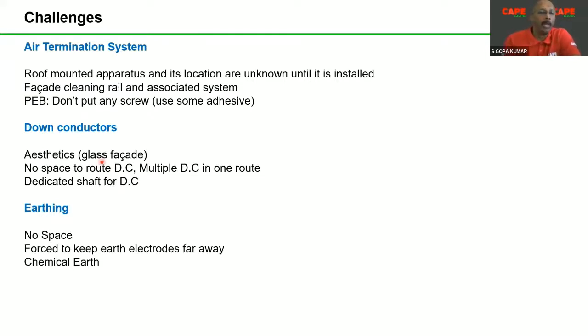You route all the down conductor through one side of the building. So all the three sides are glass. You cannot touch that particular part. Your whole lightning protection down conductor has to be routed through one side. Practically, this is a violation of the standard. Your lightning protection system will not work.